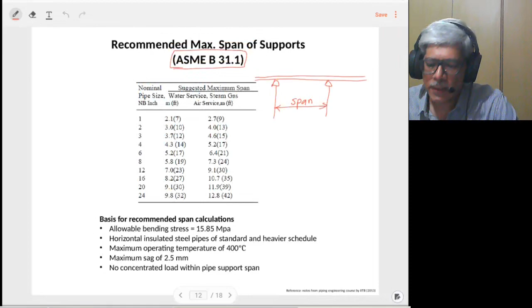So if you look at this table, you'll find that for different pipe sizes, the maximum spans are given depending on whether it is water service or steam or gas or air service. The maximum spans are defined. So this you can take as a guideline to decide how many supports you require over a particular length of a pipeline. And you will observe that it depends on the pipe size.